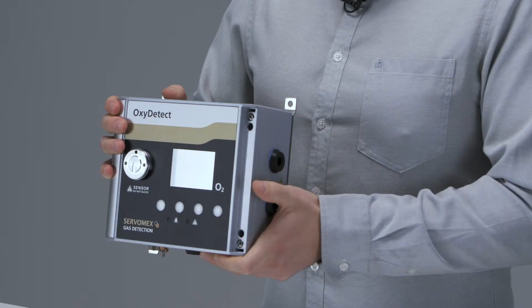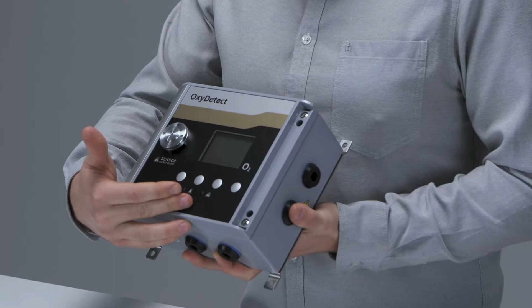The OxyDetect has a number of exterior features. We have the display and keypad here on the front, the calibration piece. We also have our alarm and fault LED indicators. We have a number of conduit entries on the outside for cabling, earth stud, an enclosure breather, and here on the side our rating and ID label with the all-important serial number, and optionally a hazardous area certification label here on the top.